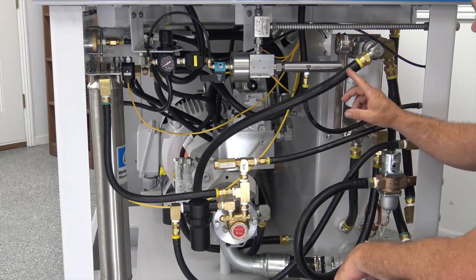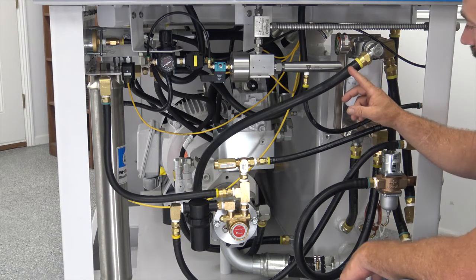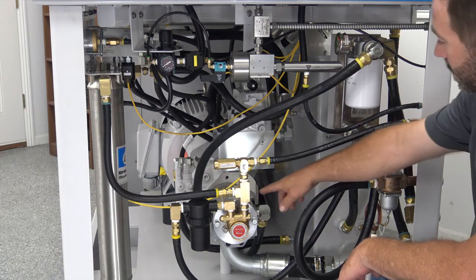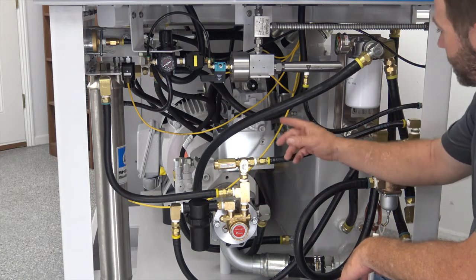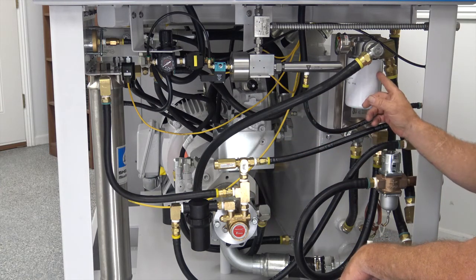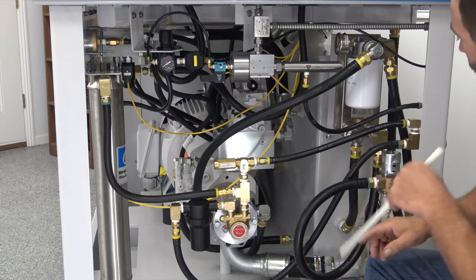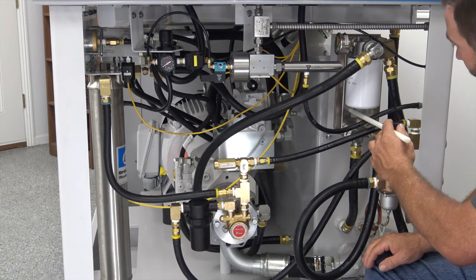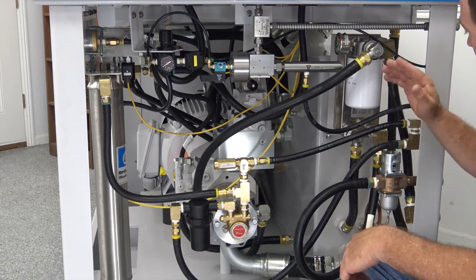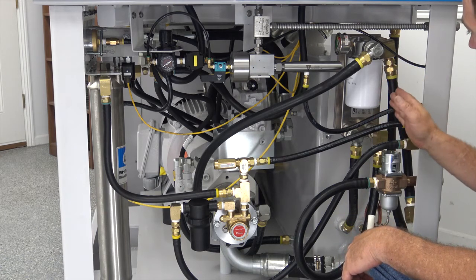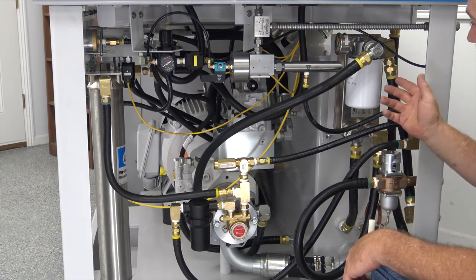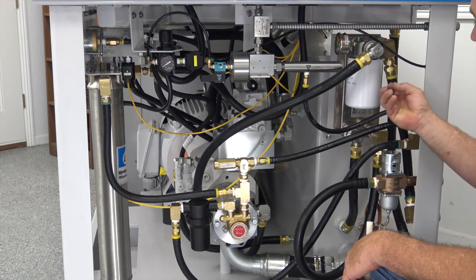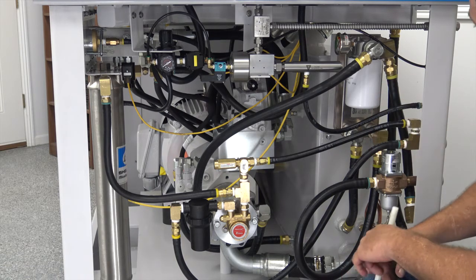This is the way that your pump cools the hydraulic oil. It sucks in, of course, through your recirc pump, comes through, goes through the filter, goes into the plate exchanger, which you'll see is in the back. And one side of that plate exchanger's got oil running through it, the other side's got the water running through it. And that water to oil is how that transfers the heat out of your machine.